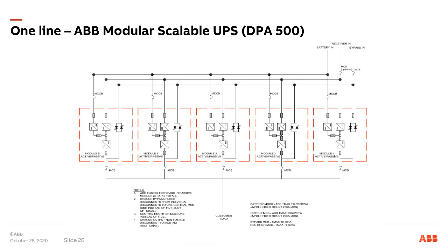So this is slightly bigger, but that's one line. That's actually a 500 kW UPS. You close the doors and it operates. It supports 500 kW, but it's actually 5 100 kW 480 volt UPSs in parallel. They all have their own control logic. Every single one of them can control the operation of the entire system, but it operates like a 500 kW UPS. And because of the decentralized design, it offers a true N+1 redundancy up to 400 kW.